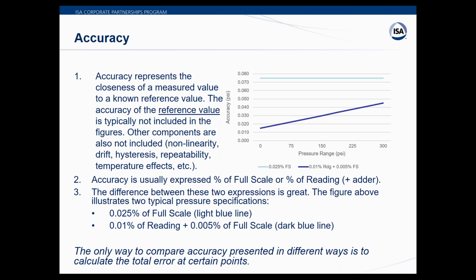One thing that's really important here, when you look at a specification for accuracy, since you're comparing it to a known reference value, is to consider how accurate the instrument was that helped you establish the accuracy statement. It obviously needs to be more accurate than the instrument that you're saying has a certain accuracy. In addition to that reference value, when you state accuracy, there are other components that can impact performance and quality of the measurement, and we've already kind of listed these. So drift is a big one. Does it drift a little bit, a quarter percent a year, a half a percent a year? And if it's in a hostile environment that can be very hot or very cold, how does that affect the transmitter or instrument's ability to make a measurement?